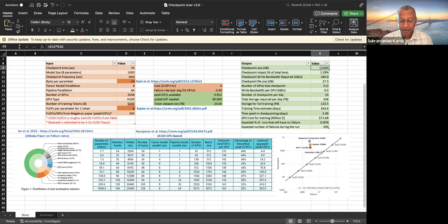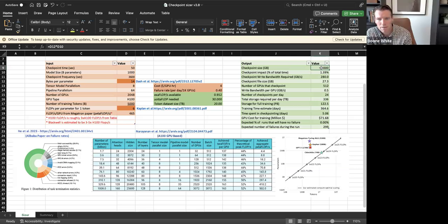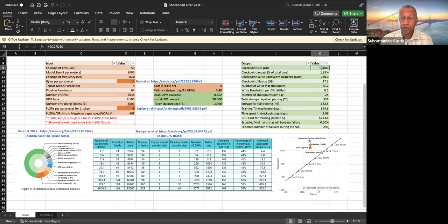The next generation of the Blackwells, especially the MGX versions, the NVL72s from NVIDIA, have like a 120 kilowatt rack requirement, 120 kilowatts. So you can imagine, if you're taking in that much power, you're going to put it out as heat. So these get hot very soon, and they are power hungry beyond belief. And typically you add about 20% more on the cost for networking and cabling. I've seen installations that we've done where the cabling is 10 kilometers of cable just to support 1,280 GPUs. It's massive. It's really, really massive, all InfiniBand networking.